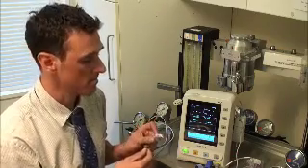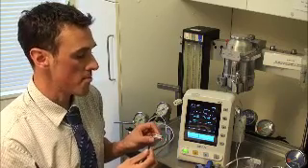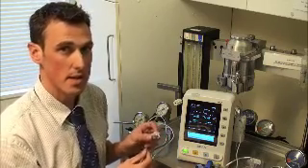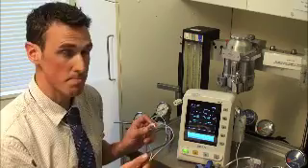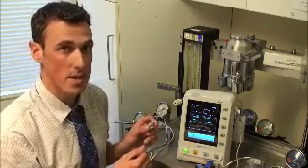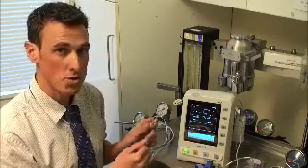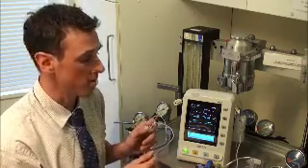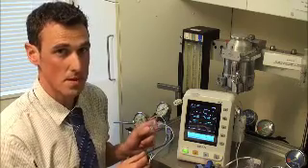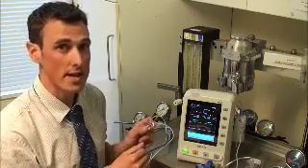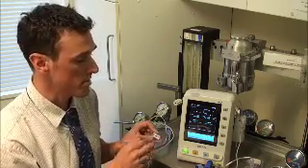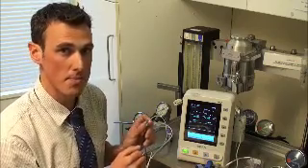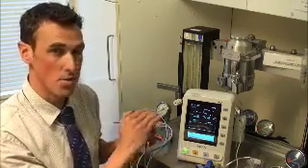It is worth remembering that during the course of the anaesthetic, the capillaries across which it is measuring will become compressed, and therefore periodically you should move and moisten the probe and reattach to make sure you do not get an erroneous readout. Also, overhead fluorescent lighting will affect the interpretation that the machine actually picks up, so it is worth protecting this using strategic draping. And that's it, you're up and monitoring.